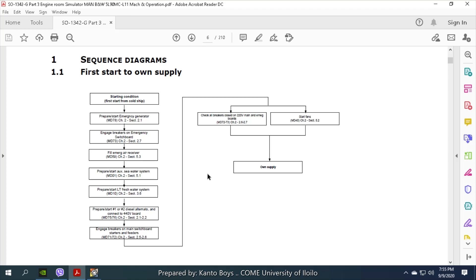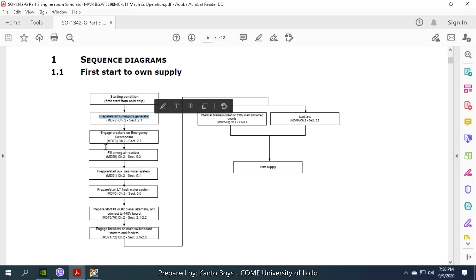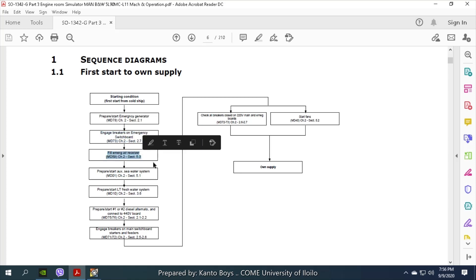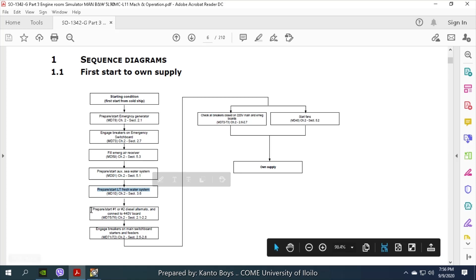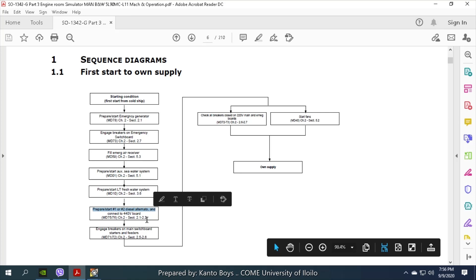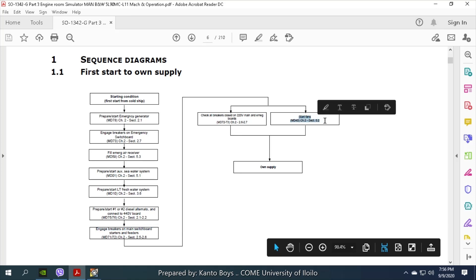The topic to be discussed here is Cold Ship to Own Supply. This is the sequence diagram to start Cold Ship to Own Supply. The starting condition is cold ship. The sequence is: prepare the emergency generator, engage the breaker and emergency switchboard, fill the emergency receiver, prepare seawater system, prepare and start low temperature fresh water system, prepare and start diesel generator one or two, connect to bus bar, engage breaker and main switchboard starter and feeder, and finally start the ventilating fan.